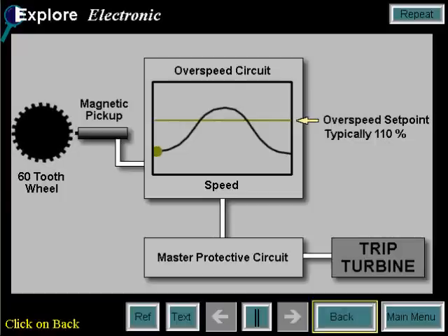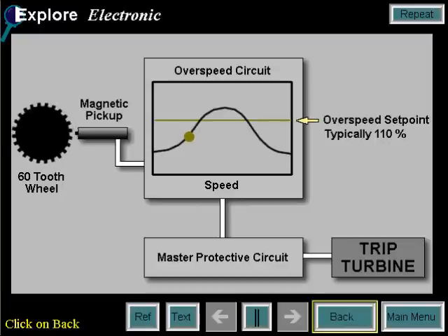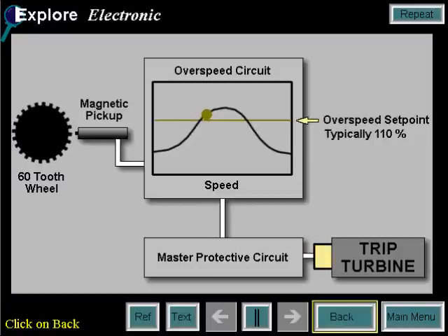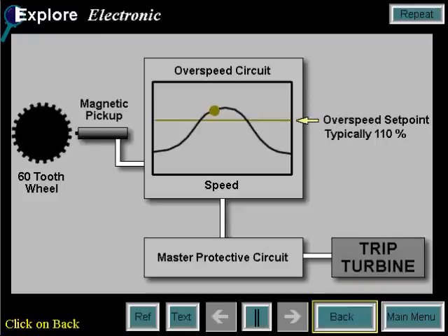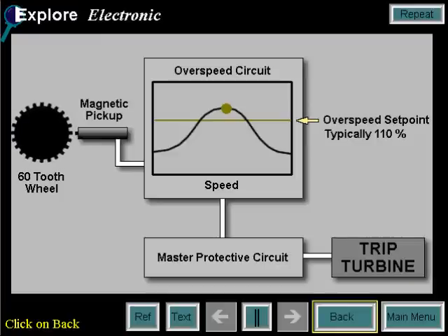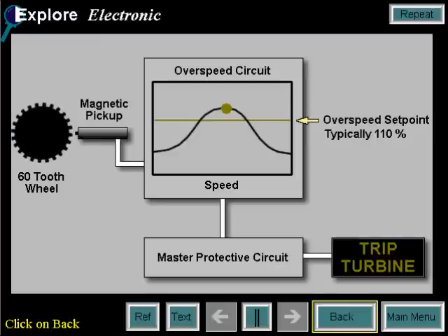The electronic overspeed protection function is performed as follows. The turbine speed signal derived from the magnetic pick-up sensors is compared to an overspeed setpoint. When the turbine speed signal exceeds the setpoint, the overspeed trip signal is transmitted to the master protective circuit to shut down the turbine. An electrical overspeed trip message will be displayed.